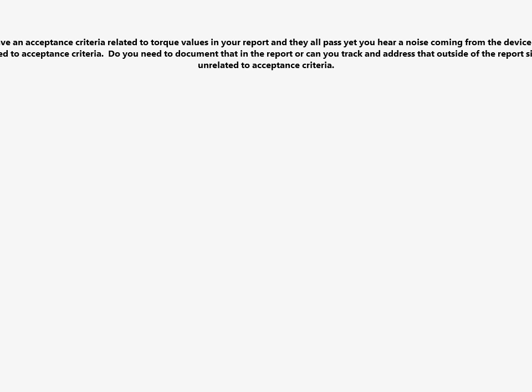Yeah, is that noise, or whatever's going on, in relation to torquing the device? You're torquing the device because it gets torqued clinically. So what's going to happen when a physician torques the device and hears that noise, and what kind of effect is that going to have on the patient? I would have to know more for sure, but it's something to definitely look into there.